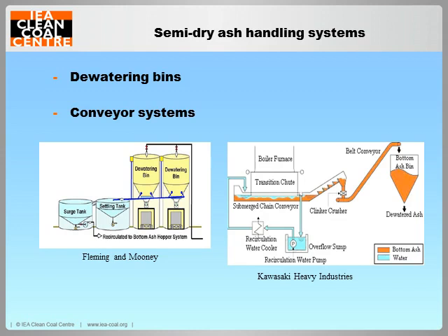In the conveyor system, which is shown on the right, the bottom ash is removed by a conveyor which is submerged in the water trough below the boiler as the ash is quenched by the water. The ash is then dewatered as it travels up the inclined section.